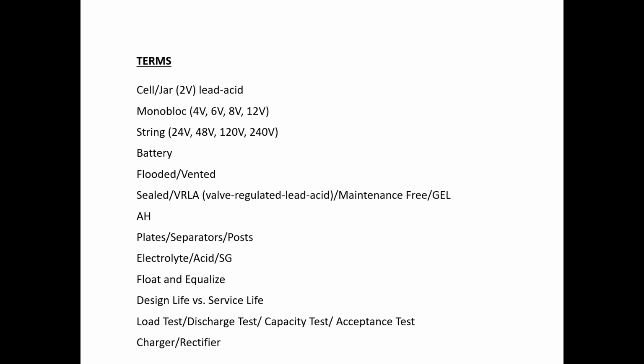Electrolyte, acid, specific gravity. You don't really have the luxury of checking the strength of the electrolyte. It's sulfuric acid-based. The higher the gravity, usually that kind of juices the cell. It's higher performance. A specific gravity of 1.215 and 1.30 are kind of standard in lead acid batteries. At 1.215, same battery, less performance. At 1.30, higher performance. The thing with the higher gravity, though, is you accelerate your corrosion rate. So there's a trade-off. You get better performance, but you kind of have to design around a shorter service life.